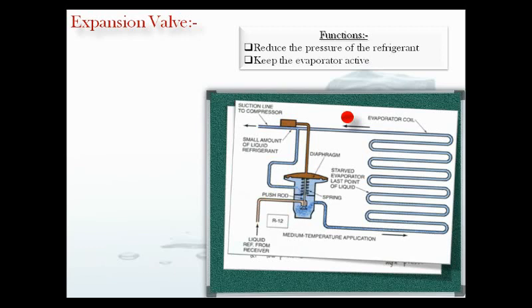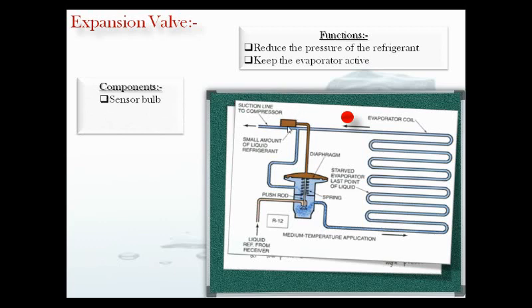The valve needle remains open during the steady state of pressure. The size of the opening, or the position of the needle, is related to the pressure and temperature of the evaporator. There are basically three main parts of the expansion valve that regulate the position of the needle: first is the sensor bulb located at the end of the evaporator coil, which monitors the temperature change of the evaporator; second is the diaphragm, where a change in temperature creates a change in pressure; and third is the needle valve.